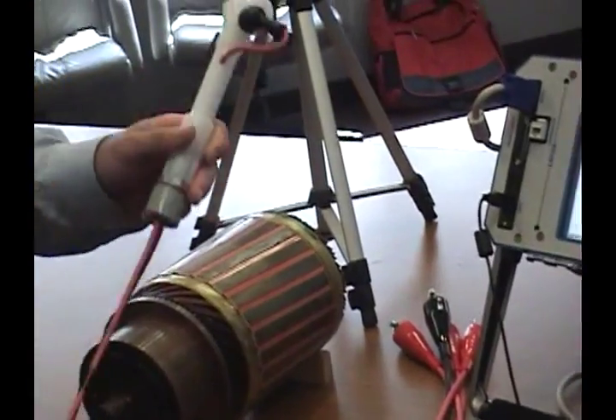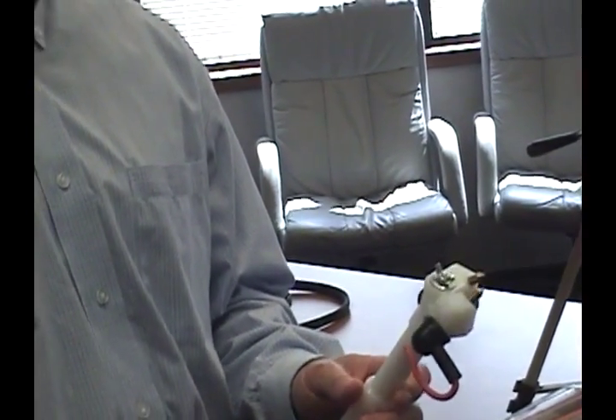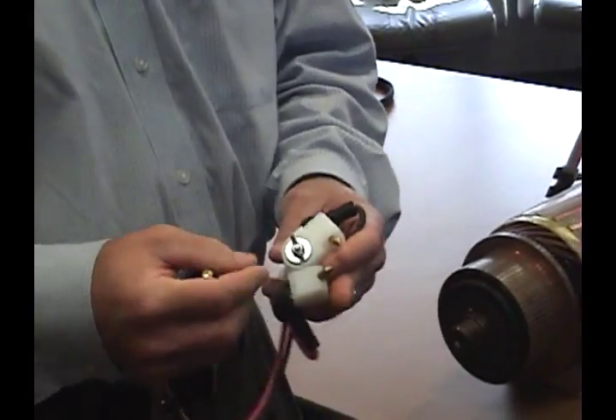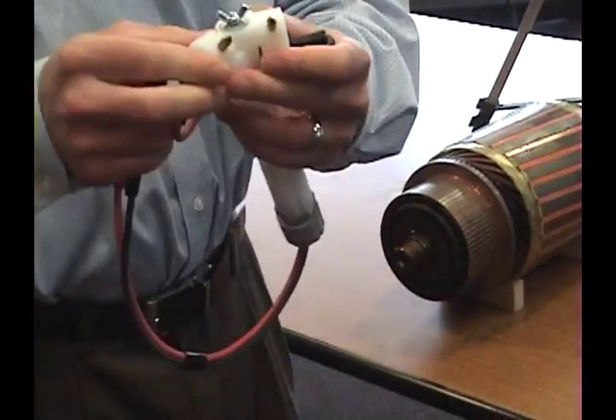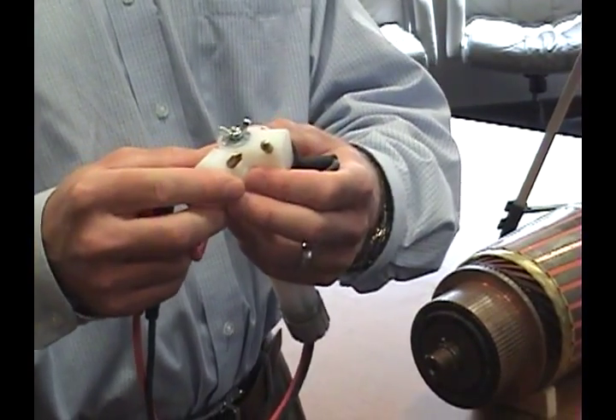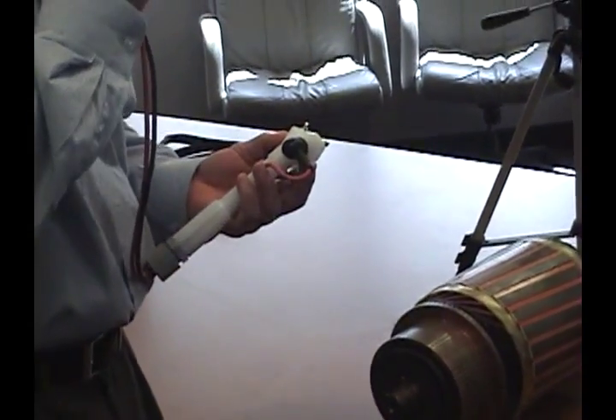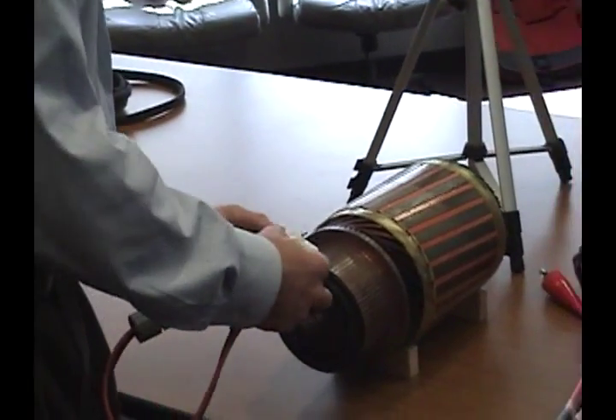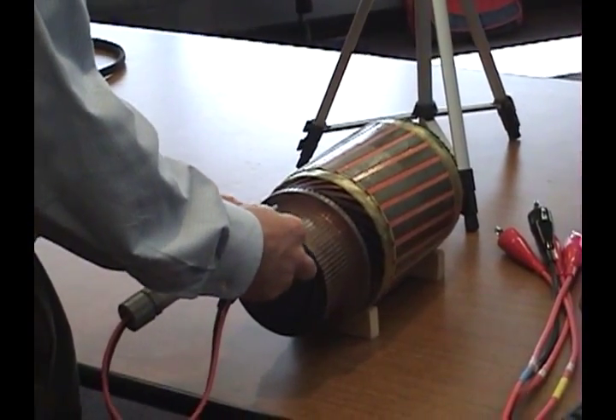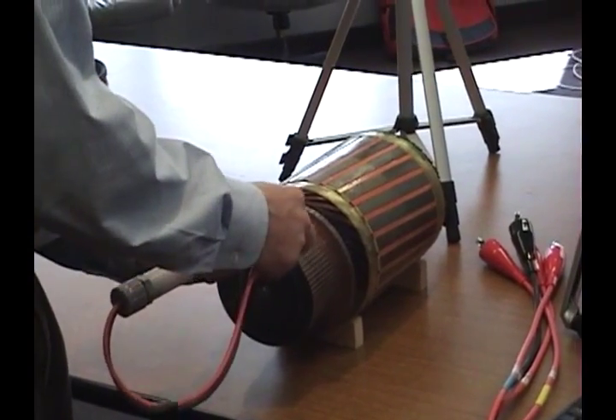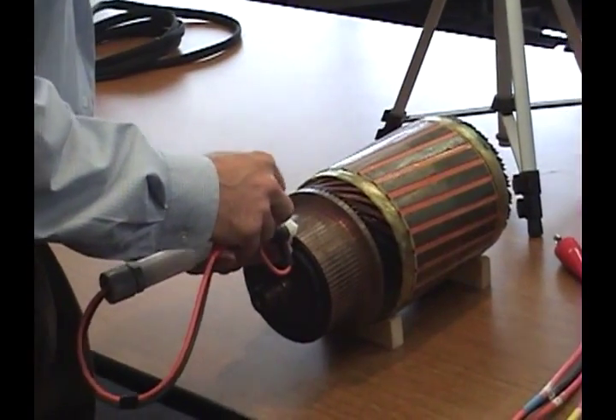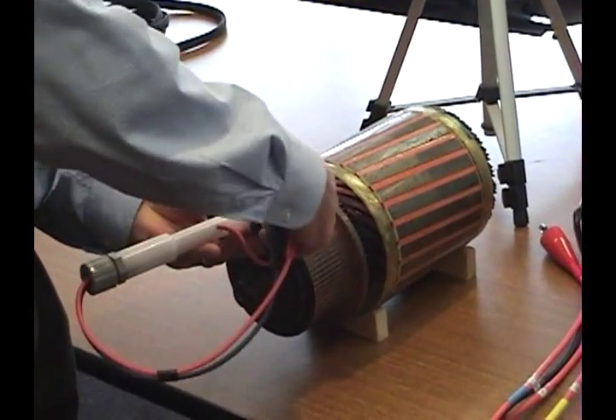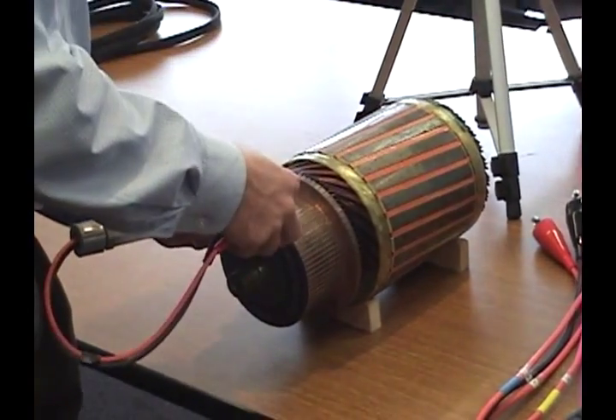We will also be using the ATF-02 to perform the span test. We have a wing nut here that we will loosen up and we can open and close depending on the width of the bars. The first thing we want to do is span across four bars. So we count across four bars, get our span set, and then tighten up the wing nut.